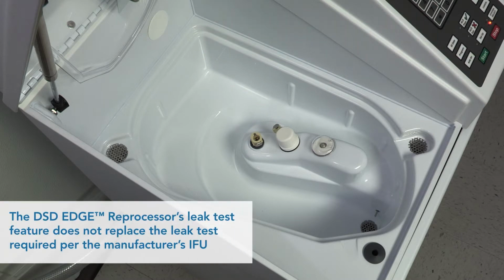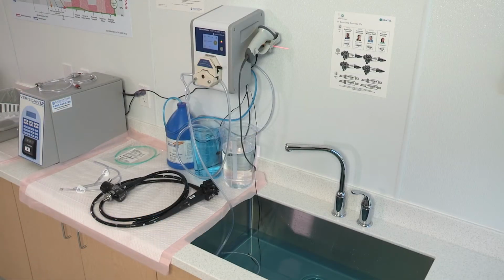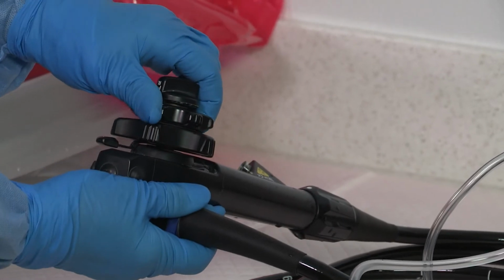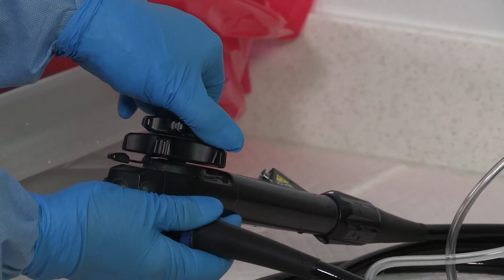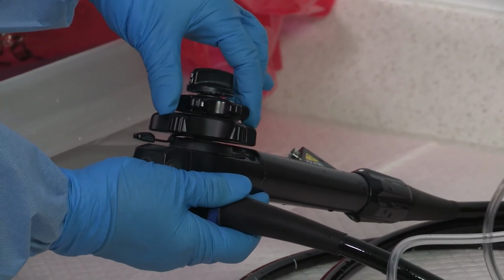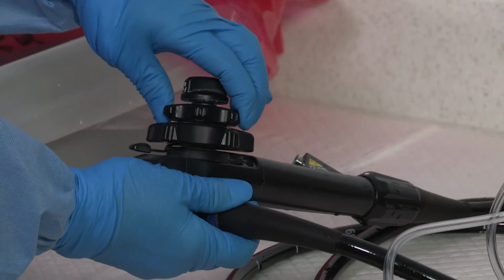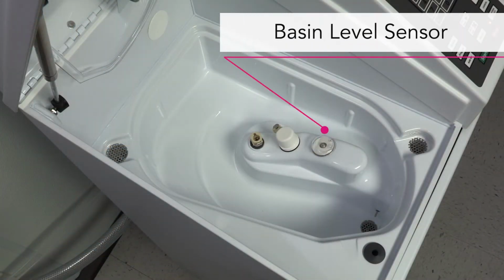Although the DSD EDGE Reprocessor has a leak test feature, it does not replace the leak test that is required by the endoscope manufacturer's IFU. The manual leak test allows for the physical turning of the control knobs to flex the bending rubber and pressing the camera switches to test these additional areas for leaks. The basin level sensor detects when the correct fluid level is in the basin, which ensures endoscopes are in contact with the Rapicide PA disinfectant.